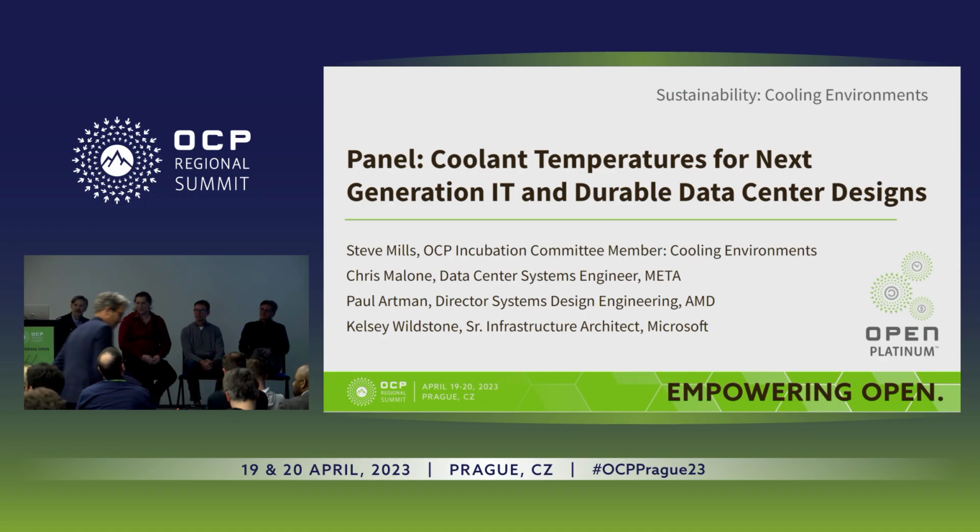Anybody else? Yeah. John Gross with JM Gross Engineering. This question is directed at Paul. You referred earlier to the secondary temperature classes that are coming out in the book. My understanding from our conversations, because I've worked with you on TC99, is that the end game is that much like the air classes turned into server manufacturers publishing that they're manufacturing the server to operate in an A1 or an A2 environment, the same thing is intended to happen with these new secondary loop temperature classes. Exactly. You want to have a common point between the manufacturer and the consumer.